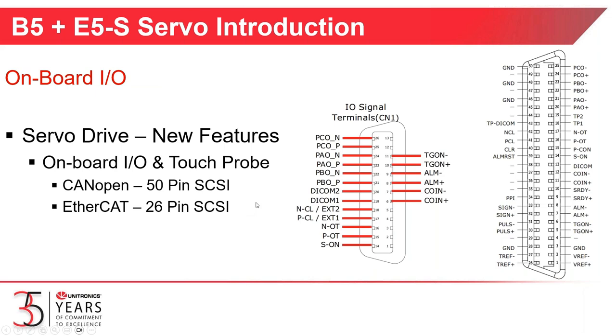Both servo drives have onboard I/O and touch probe capabilities. The CANopen drive will be shipped with a 50-pin SCSI connector. The EtherCAT drive has a 26-pin SCSI connector — this is the CN1 IO terminal on the drive. The older EtherCAT drives had a 20-pin SCSI connector, and the new drives will have 26 pins.